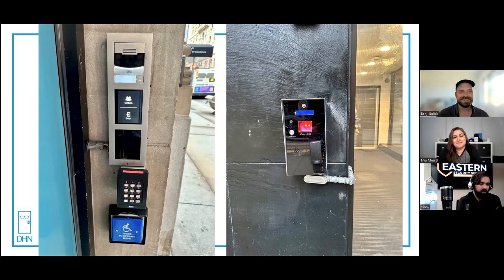The aesthetics alone of this really are cringeworthy to look at, because as an installer, there's so many times where we go to an older building, an older brick building or something, and they know exactly where they want something. You walk through it first, like, oh, that's impossible, you're going to have to use conduit for that. But then you actually start looking above ceilings, behind walls and everything, and you realize there's usually a route to get the wire there. I'm sure this was preventable if they took the time to do it right.